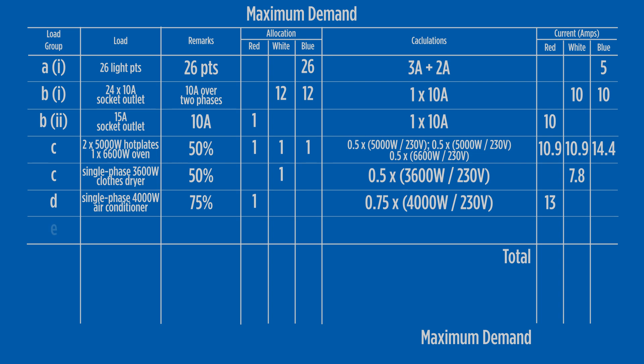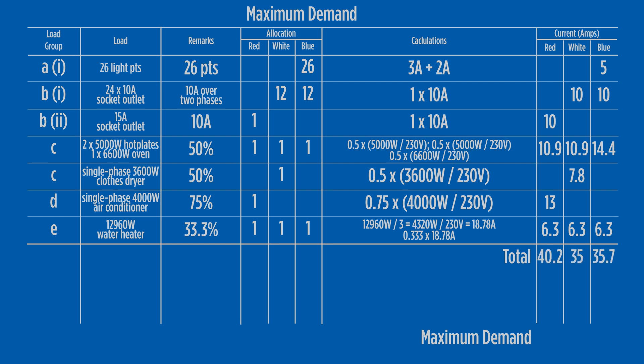Next, we introduce load group E, which covers instantaneous hot water systems. These three-phase loads will contribute the same loading to each phase. The calculation is 33.3% of the connected load, which gives 6.3 amps per phase. When the current value of each phase is added together, the red phase is the highest loaded of the three, at 40.2 amps. This value will be the maximum demand of the installation.